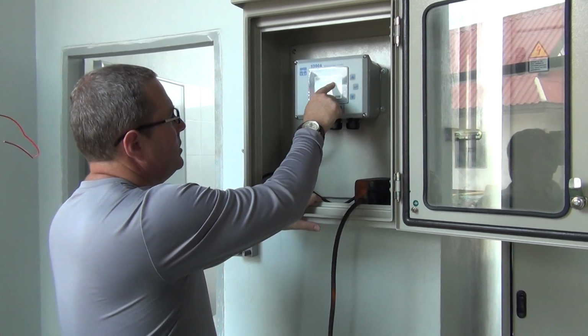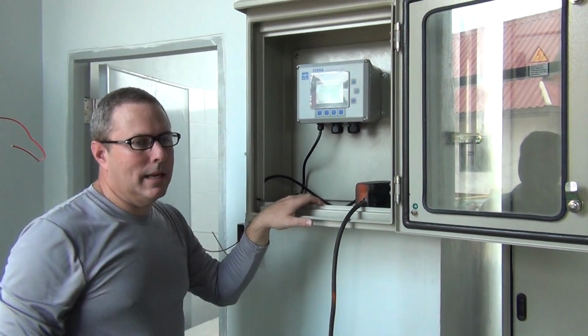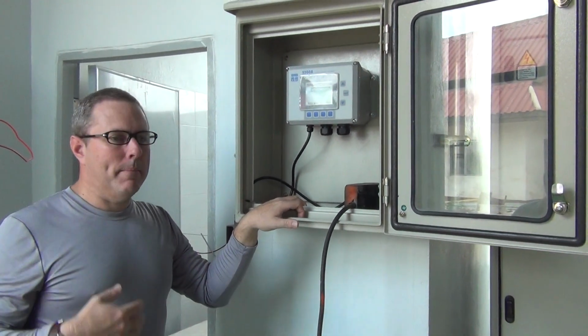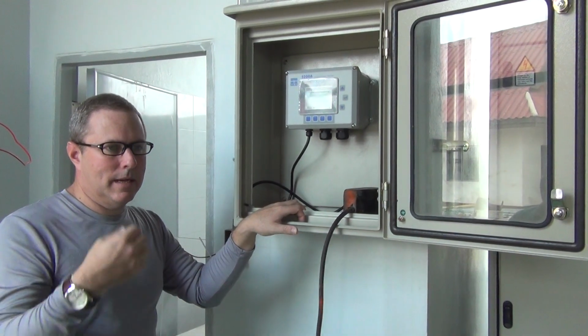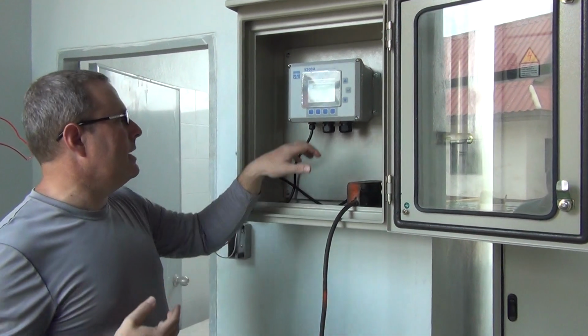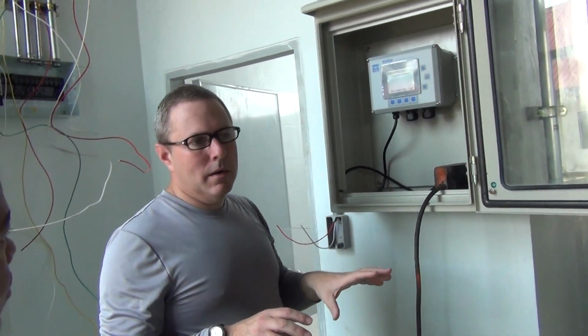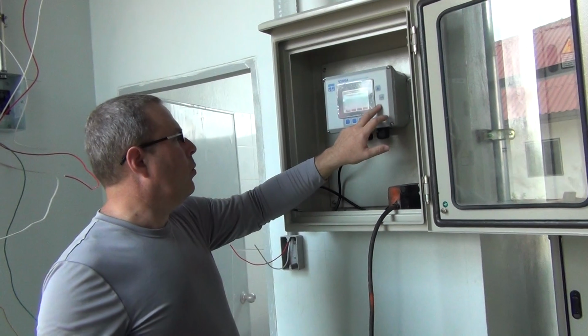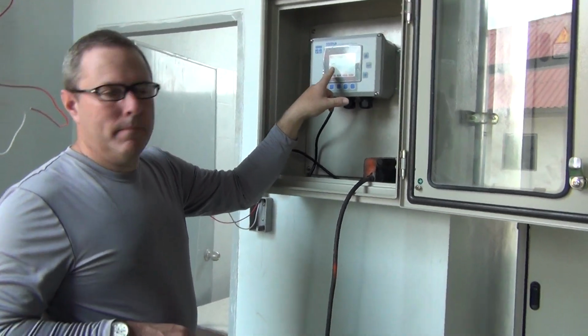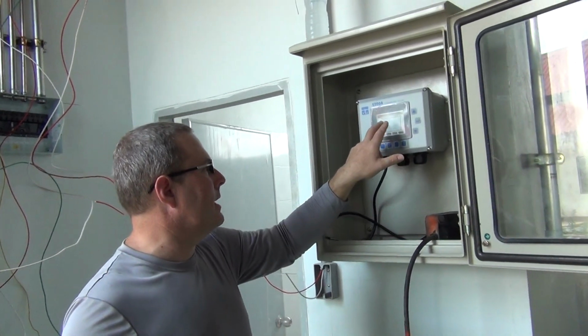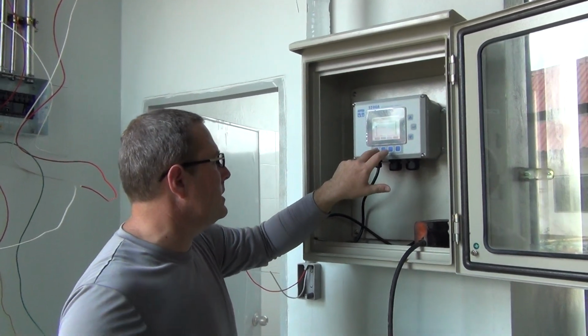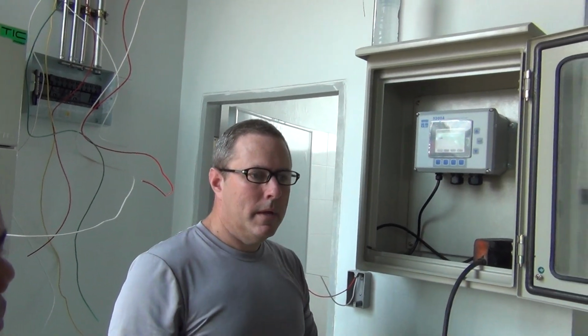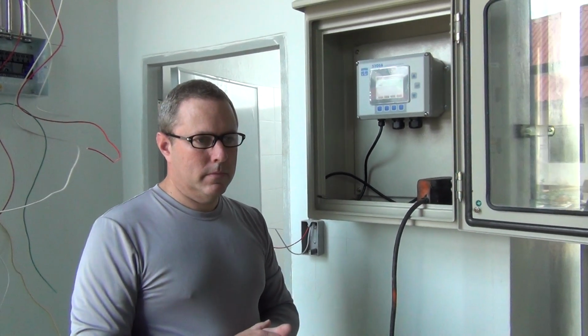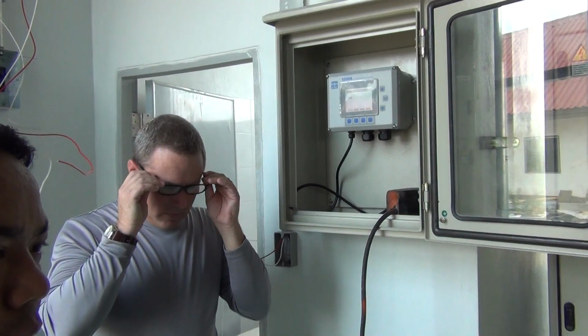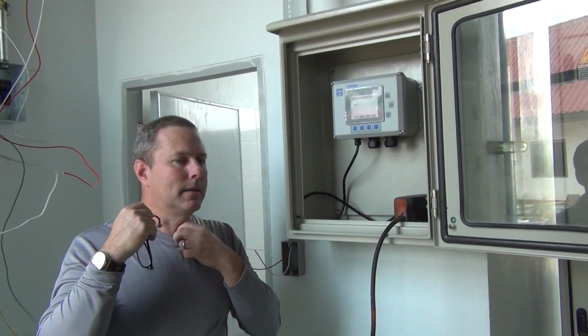For example, I would suggest typically 2 weeks is a good number for probe cleaning. So you could go here and set the duration to 14 days, or 2 weeks. Now, this then tells you clean probes enabled, 14 days left. So each day it would drop by 1 day. Tomorrow it will say 13 days, the next day 12 days. And that's going to send you a reminder on the software that the probes need to be cleaned. When you've cleaned the probes, you would go to reset, you would push it, and it says reset clean probes. Are you sure? You would say yes, and it resets the timer so that it starts the countdown again. Any questions? How long? About 2 weeks. That's what I recommend.